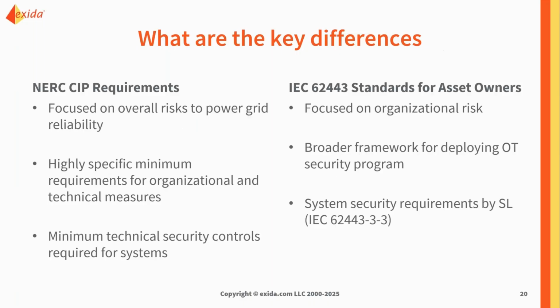If we say that conceptually the material and the concepts are aligned, the important part to understand is that there are still differences. NERC CIP looks at everything from the perspective of the power grid, so it's looking at risk to power grid reliability, which is different than looking at risk within just one organization. The way you do an impact analysis is different—it's already baked in based on the threshold and size of the facility, which facilities will have a larger impact. Whereas for 62443, it's really driven by the organization's risk matrix and risk criteria.